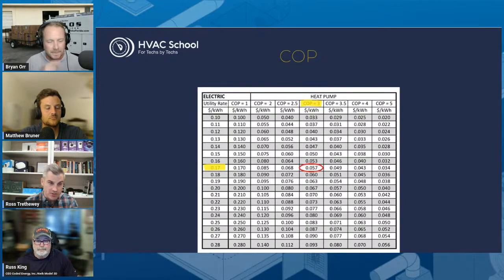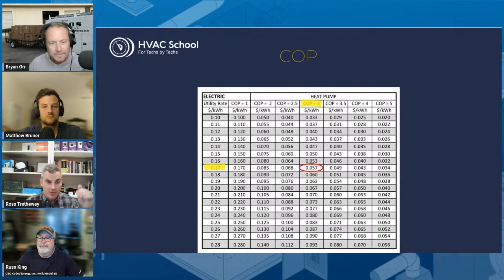We have this chart, the chart that's on the screen for anyone that's watching. You've got heat pump COPs across the top, so you can see COP 1, 2, 2.5, 3, and then obviously up to 5. The one that's highlighted is 3, and it's coming down to 17 cents a kilowatt hour, and then it comes across. What that's telling you is that your price per kilowatt hour for using a heat pump that's COP of 3 with a price of electricity of 17 cents means that it's costing me 5 cents a kilowatt hour of thermal energy. So I'm paying 5 cents, 5.7 cents technically, to get 1 kilowatt hour of thermal energy out of that.